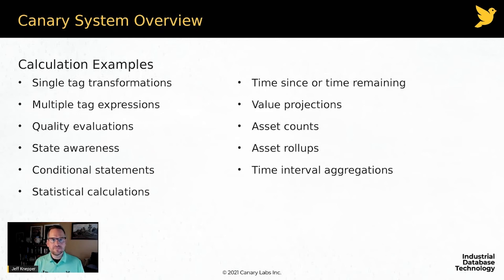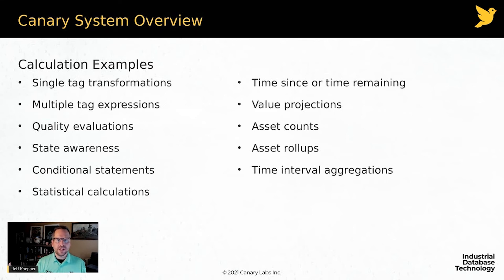Statistical calculations: we support all OPC Foundation aggregates — min, max, standard deviation, variance, population, and all standard statistical calculations. I can create calculated tags that help me understand time since or time remaining, such as time since shift start or time remaining until end of week — great for production forecasting — as well as time since batch start and time over estimated batch completion.